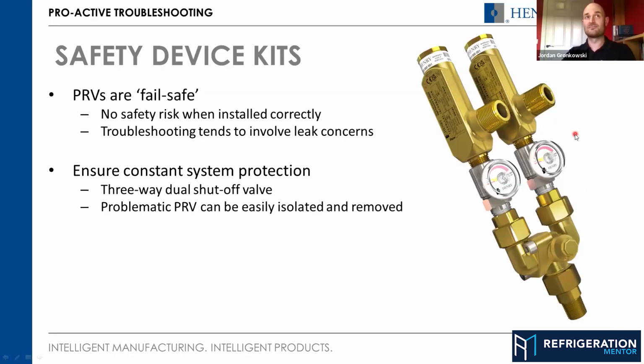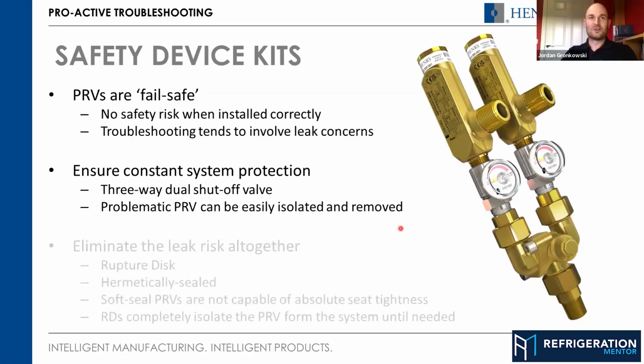Although, as I say, if a valve is leaking, maybe because of chatter or maybe because of debris in the system, there are so many reasons a valve could pass. Being proactive and having this three-way valve in the system means that it's really not going to cause you any problems, because you just isolate across to the other one, remove it, and send it away for inspection. You don't have to pull out the whole charge to change the valve, which would be a nightmare.